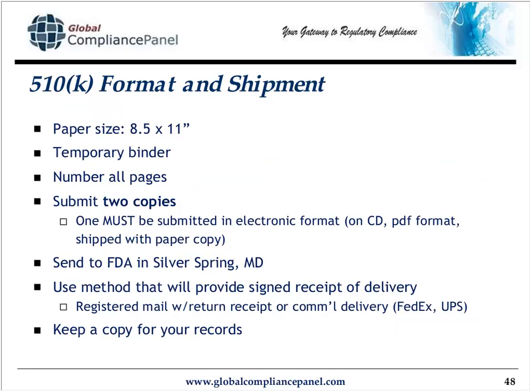When you have your 510K, the hard copy will be standard size. Put it in a temporary binder, usually a loose leaf kind of binder. Number each of the pages. This is probably less of an absolute requirement these days and more of a really good idea, because during the review of your 510K, it's going to be much easier for the reviewer to say, well, on page 73, third paragraph, please clarify this, as opposed to having to describe what's on the top of that page or the nearest page. Number your pages.